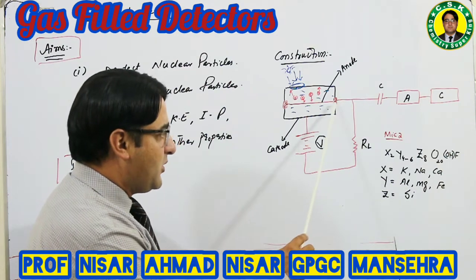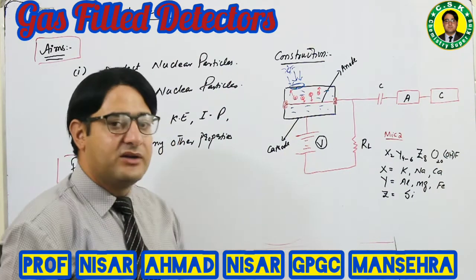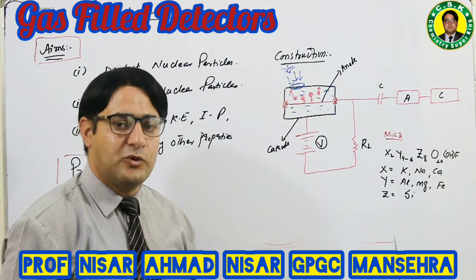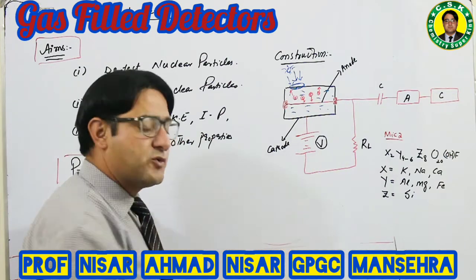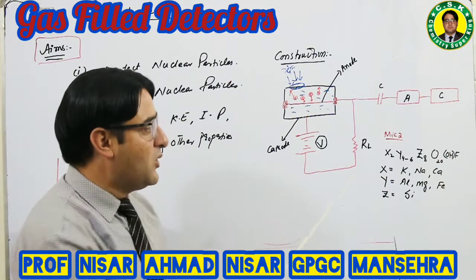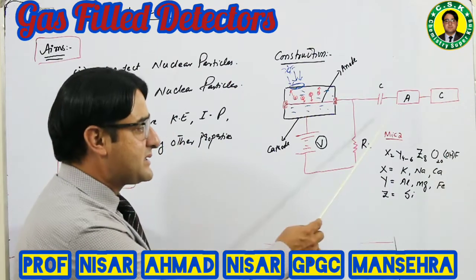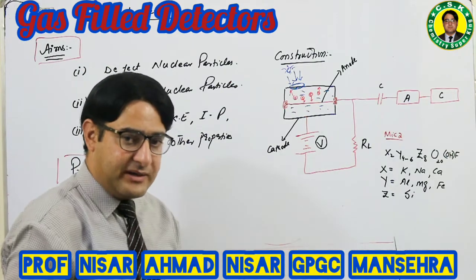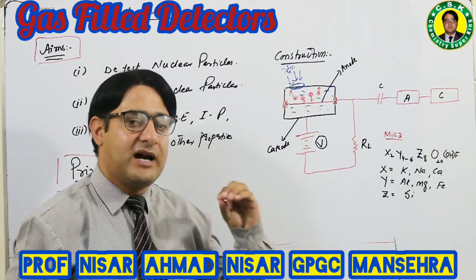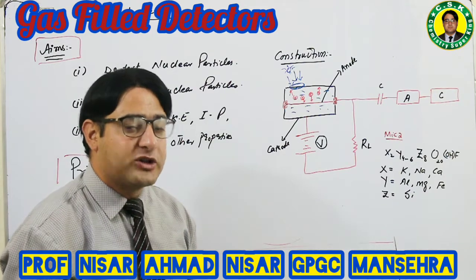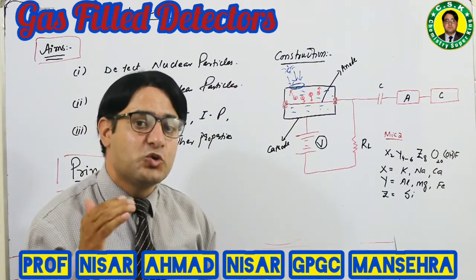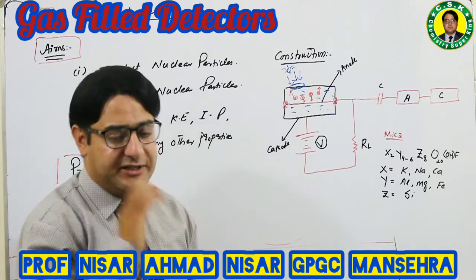There is a load resistor — when current passes through it a voltage drop occurs, generating a voltage pulse. The voltage pulse is recorded. A capacitor stops undesired noise signals, and an amplifier amplifies the pulse height. A counter counts the number of pulses. At the end we obtain two pieces of information: pulse height and pulse count, which are used for qualitative and quantitative analysis.